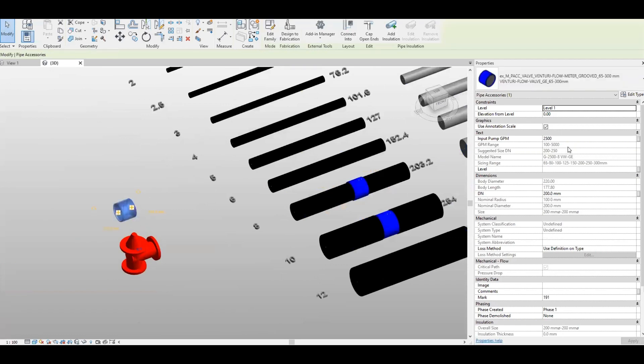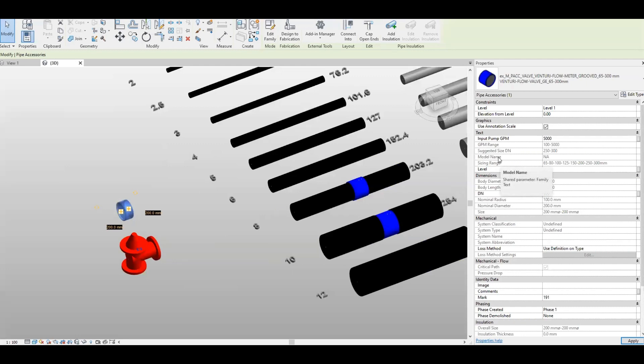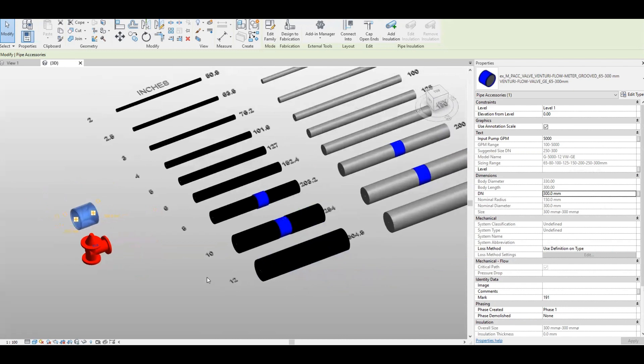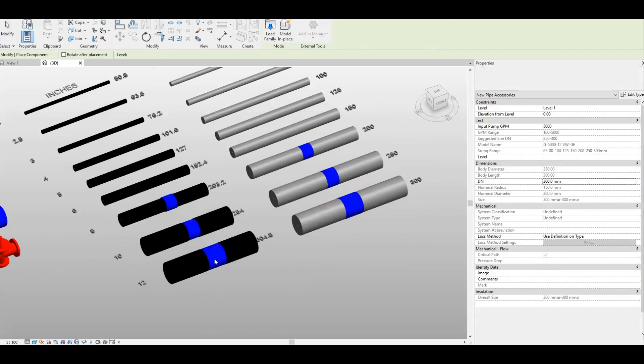Let's try to max out the sizing range — say 5,000 GPM. For a pump capacity of 5,000 GPM, the suggested size range will be 250 to 300. If you want to change it to 300, watch the model name — it will give you the correct model name. Apply. This is now the model name for 300. With this family already loaded with metric and imperial support, you just create a similar instance, click to metric and then to imperial — no problem. It will not create a pipe accessory transition.